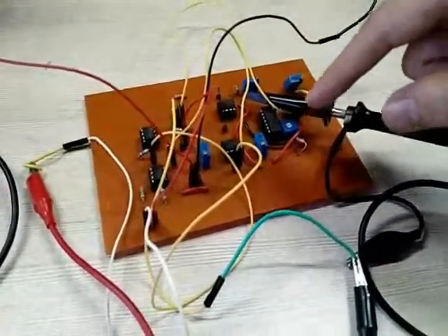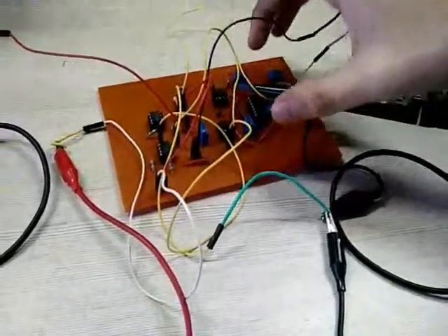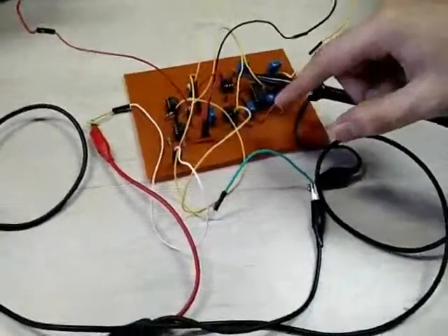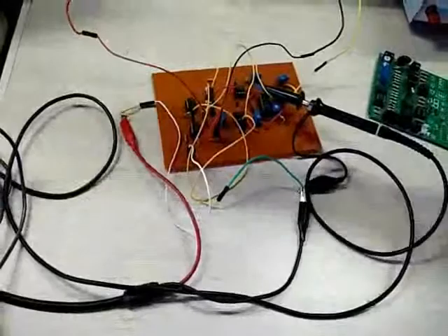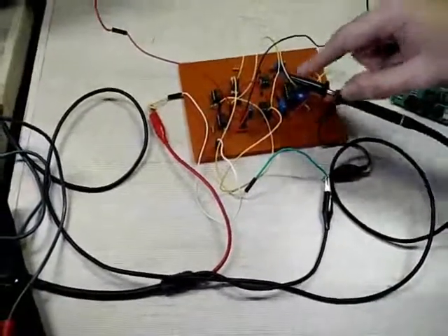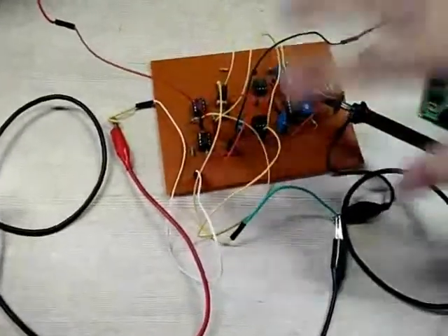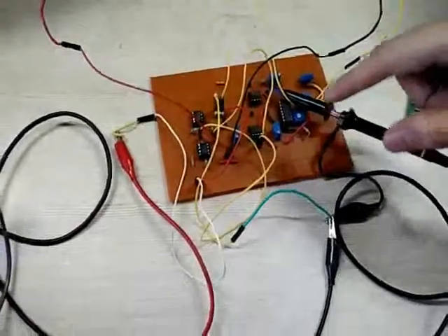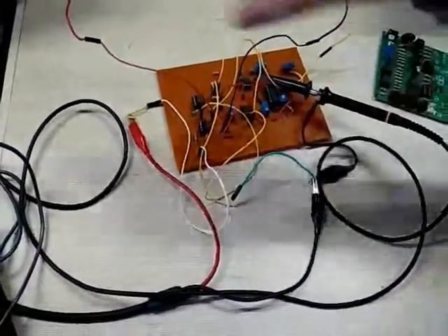So technically the gain of this data acquisition system should be around 10,000 to 40,000. But since we've used a 10 millivolt signal, it will go into saturation. So we have set a gain of 100. We have pots out here using which we can vary it from 100 to 10,000 to 40,000 as we need. So this is the output with the gain of 100. We've taken 10 millivolt, and we get approximately a 1 volt signal.